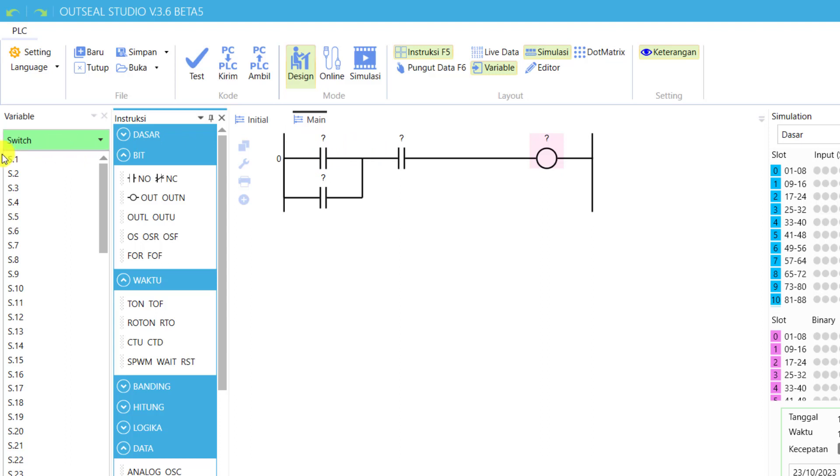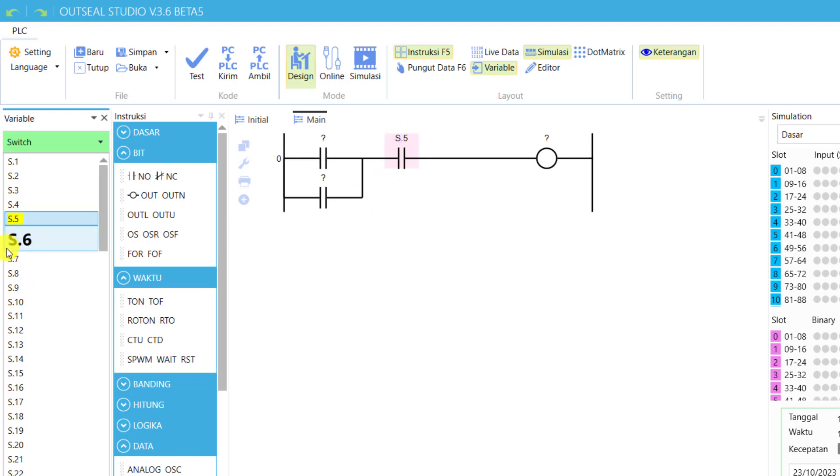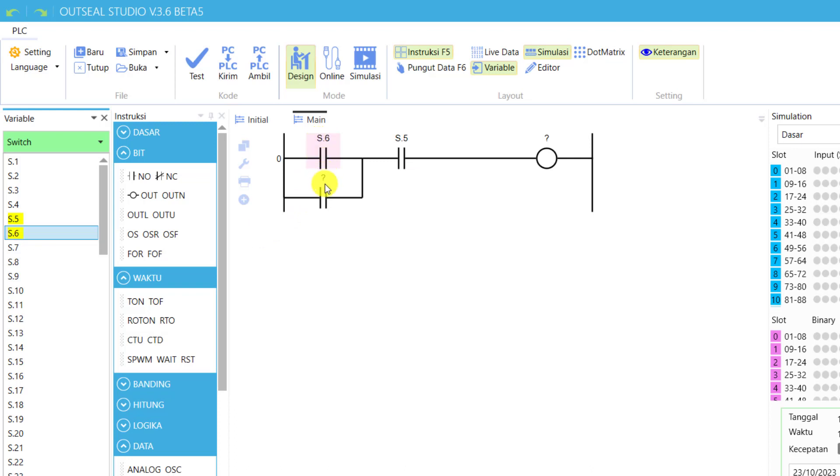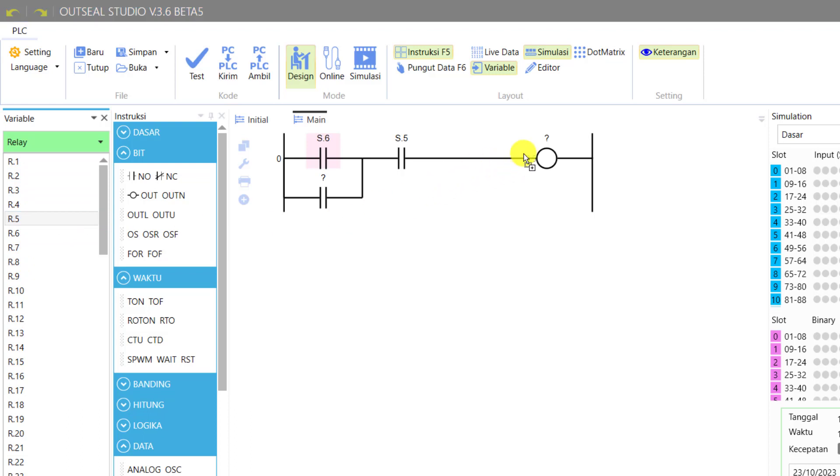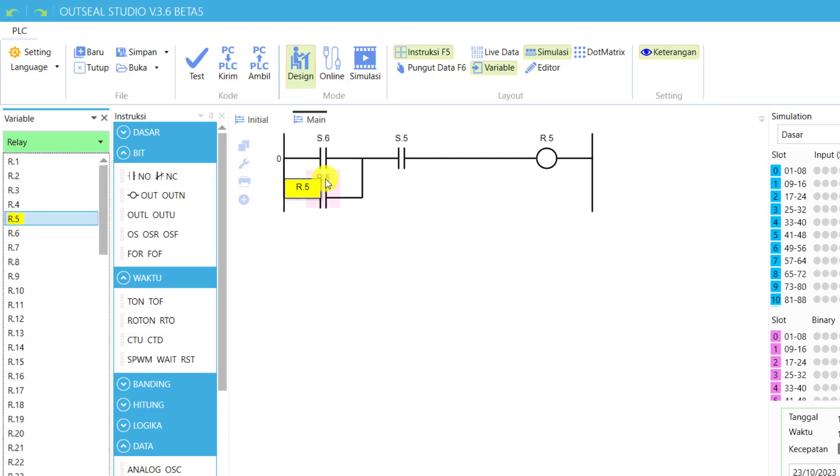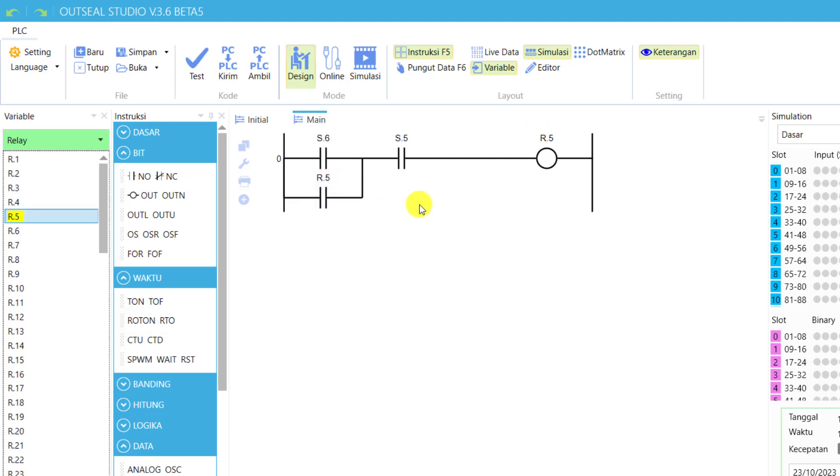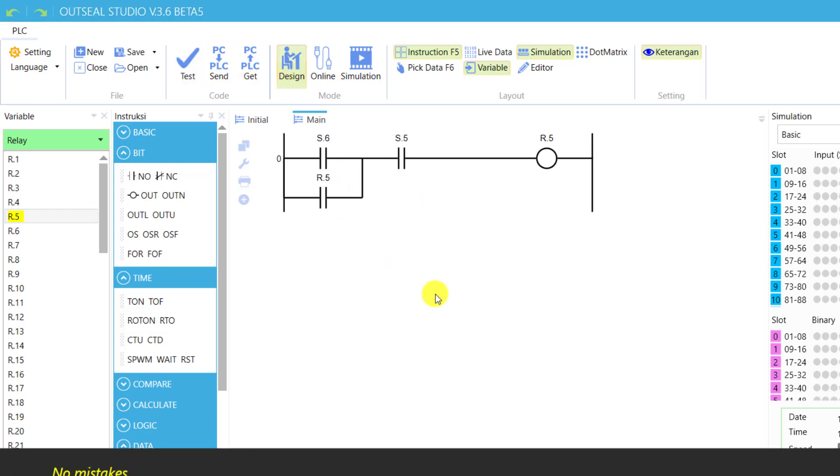We assign the addresses. We move to switches and select S5 for our stop, S6 for our start. We move to coil and select R5 for our yellow lamp, and then we assign R5 as the hold-on contact. We click on Test and we can see there are no errors, no mistakes.